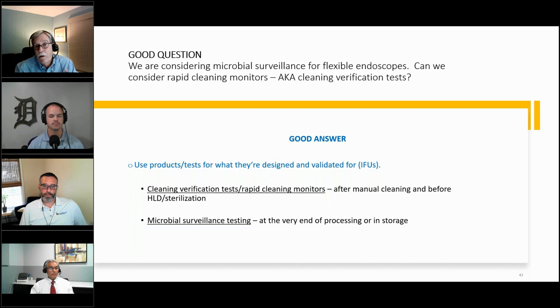On the other hand, microbial surveillance testing occurs after processing is complete, after the entire processing cycle is complete. It's used to measure, again, as the name implies, presence or absence of microbial contamination. If positive, in this case, the entire process needs to be evaluated because you could have had a gap or an error somewhere along the way from pre-cleaning through cleaning, disinfection, drying, and storage. Anywhere along the way, you could have had a failure point. Again, it's not been uncommon for even clinicians to misinterpret when to use these tests.